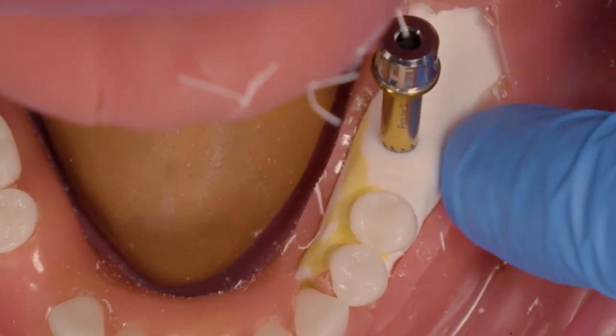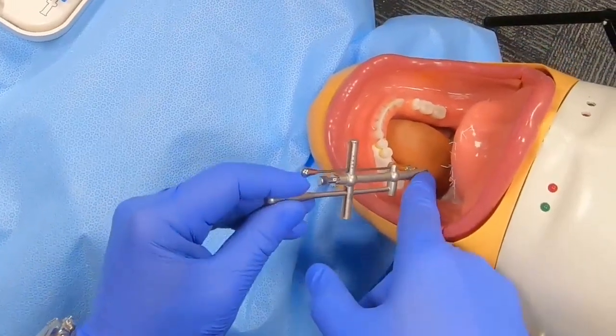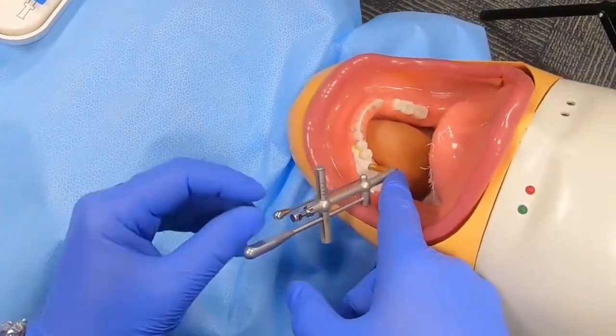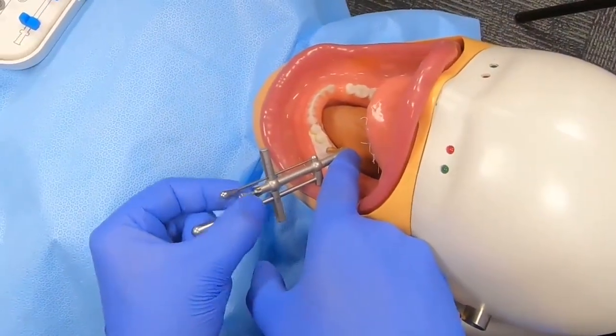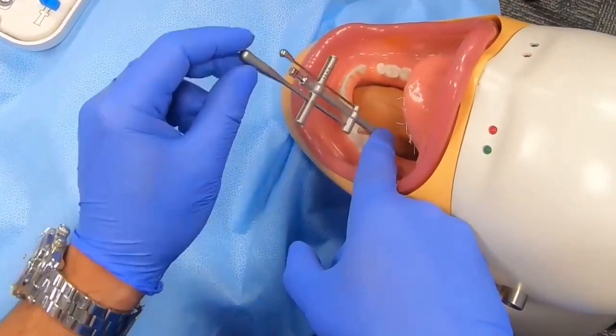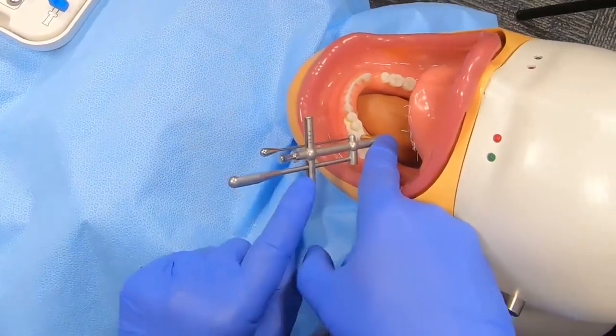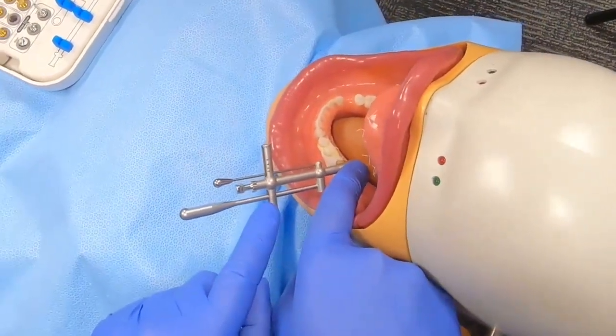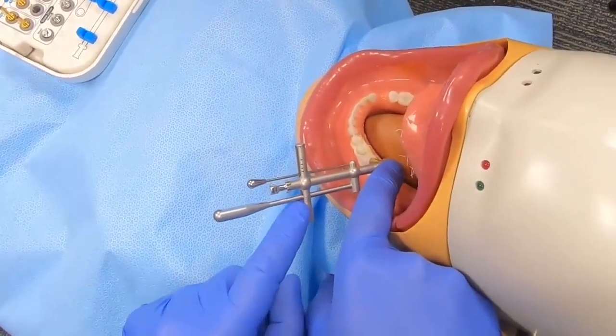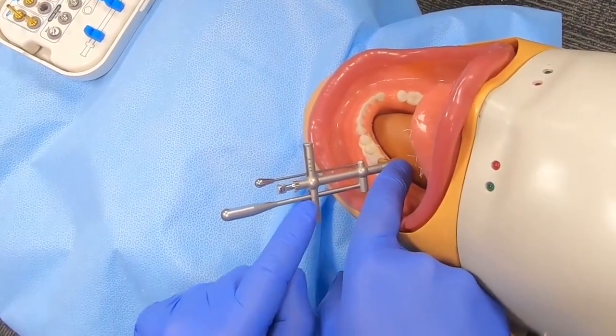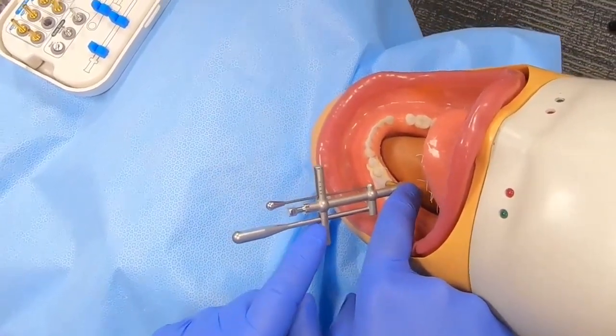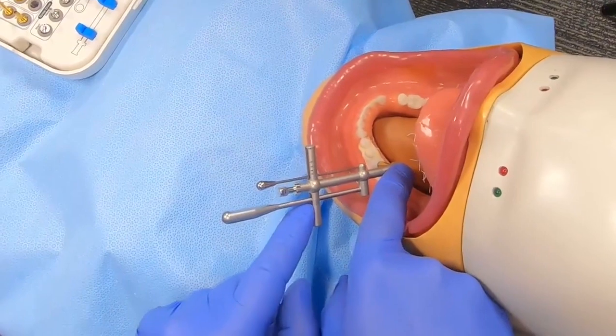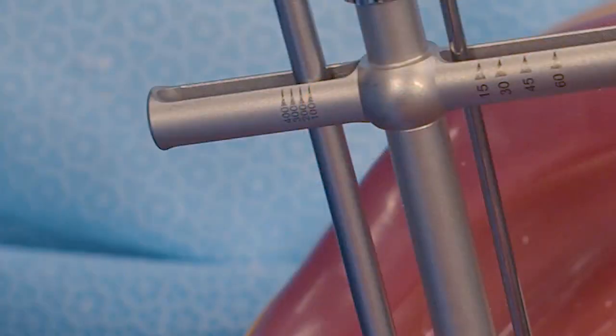And the way we're going to remove this implant is we're going to go counterclockwise. So there's the arrow here, we have to switch that. And now on the other side of the driver, which is a new feature, you can see the amount of torque you can apply on this implant to remove it. And it ranges between 100 to 400. So you can apply a significant amount of torque on this implant.